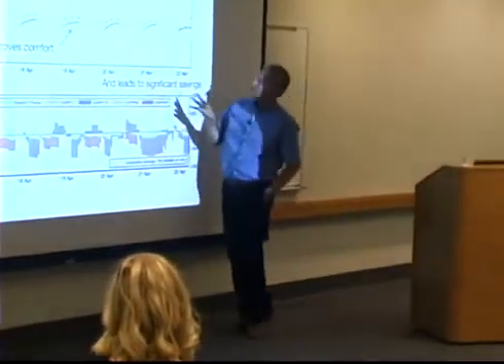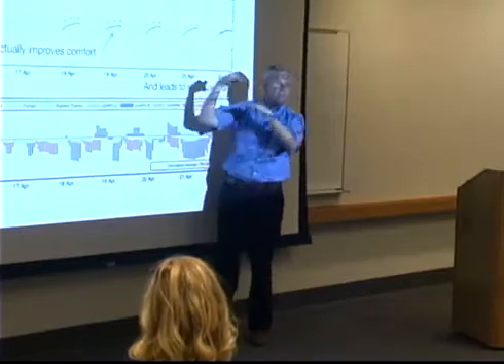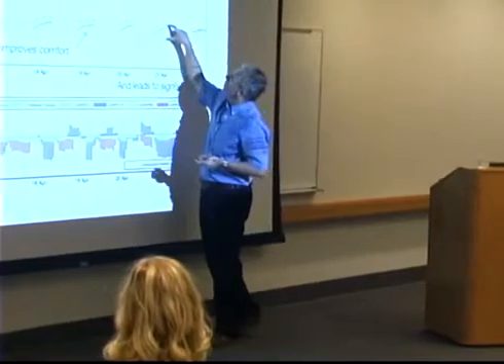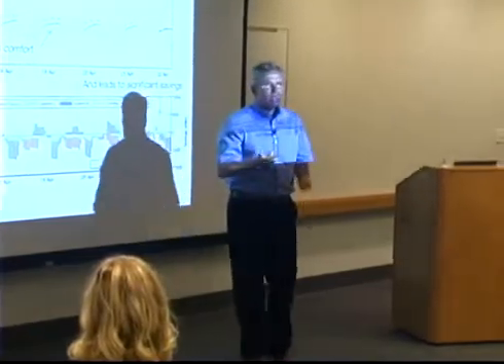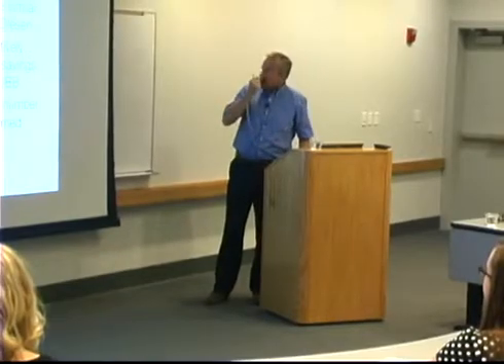But what I think is most interesting is that the MPC results indicate that the optimizer does all that by keeping the building more comfortable. Because the comfort range is that plus minus 0.5 PMV range, and the blue optimal control case lines are actually never outside the thermal comfort. So what we see here is that the optimizer has a chance of significantly reducing energy, all at the same time providing better comfort than a normal building would. So that's what we think is quite promising. We noticed in comparison with the Olesen and the unknown but bounded method that the optimal control approach finds better solutions.